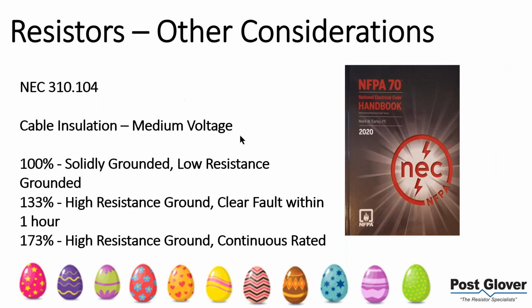One thing to talk about on medium voltage is the cable insulation. This is just going along with what I was saying before. You need to make sure you're properly rated. For solid ground, you don't have to worry about it. Low resistance ground, you don't have to worry about it. But if you were talking about high resistance ground, like I said, there are costs associated with being able to continue to operate, especially at medium voltage. So you need to look at these values and see if it's something you're interested in doing. But you have to do that because, for example, continuous rated, you're definitely multiplying by the square root of 3, so that's 173%. So that's where that other number came from as well.